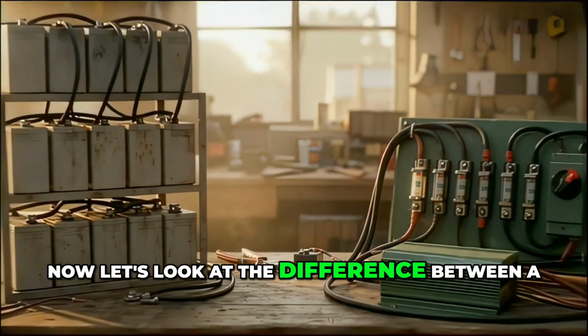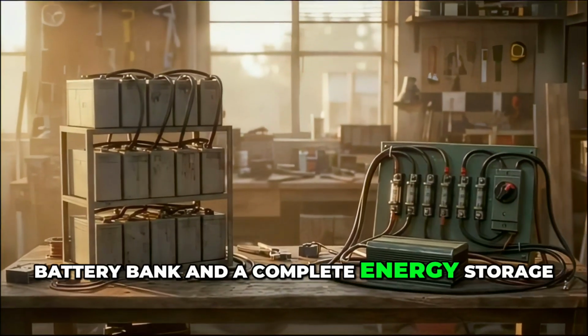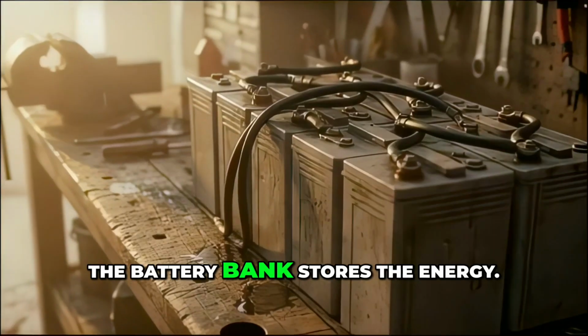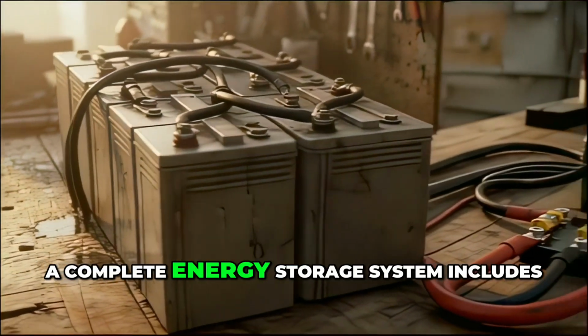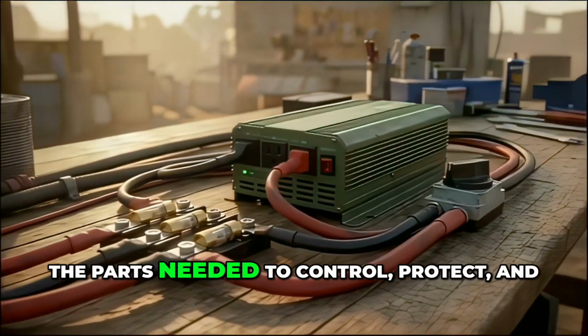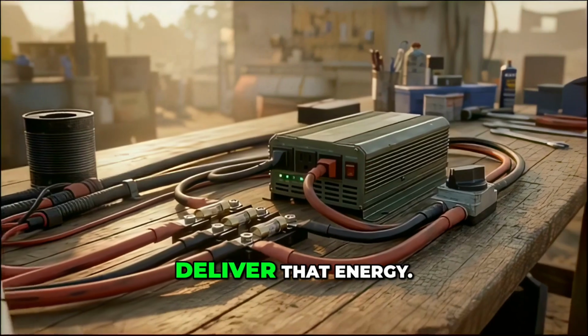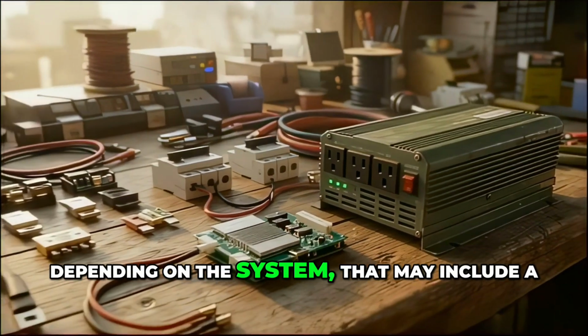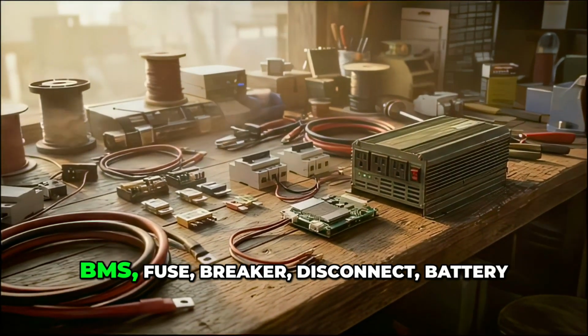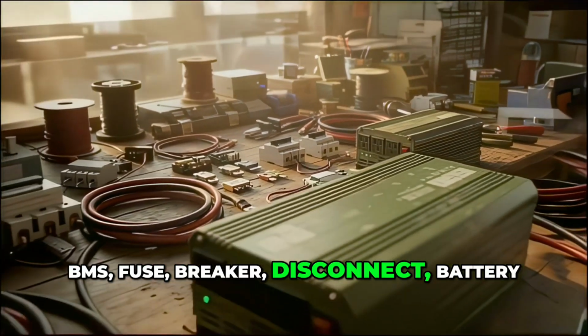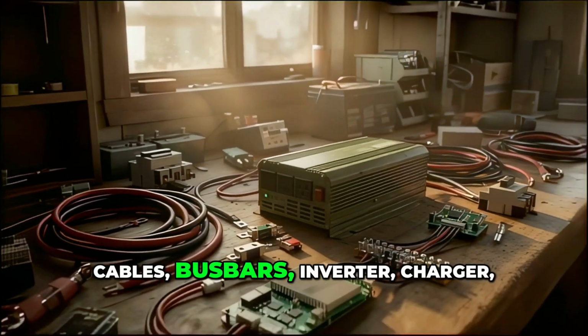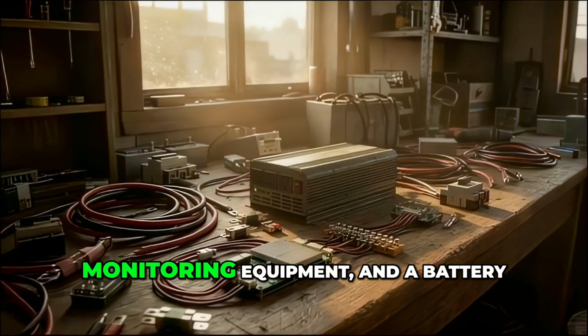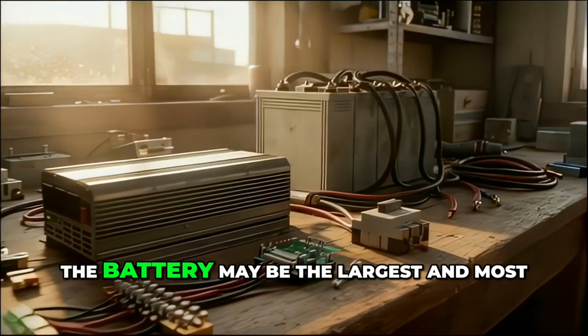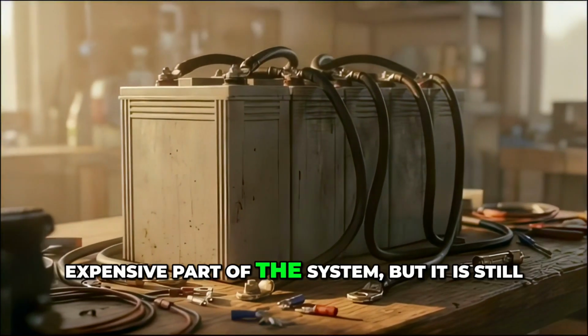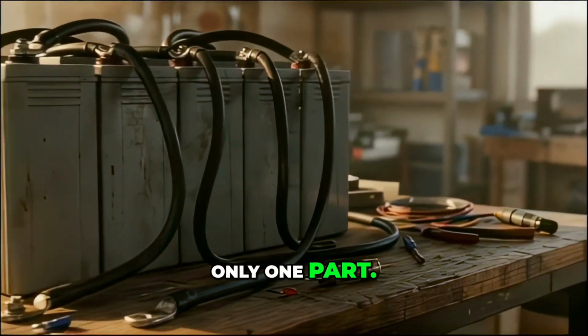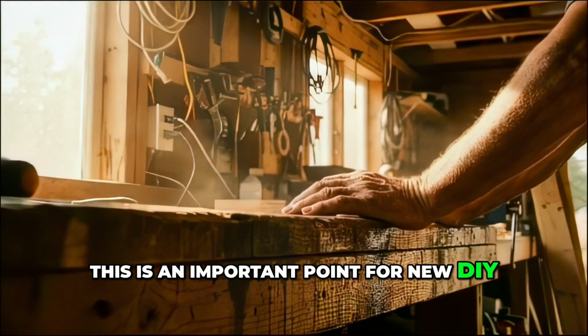Now let's look at the difference between a battery bank and a complete energy storage system. The battery bank stores the energy. A complete energy storage system includes the parts needed to control, protect, and deliver that energy. Depending on the system, that may include a BMS, fuse, breaker, disconnect, battery cables, bus bars, inverter, charger, monitoring equipment, and a battery enclosure. The battery may be the largest and most expensive part of the system, but it is still only one part.